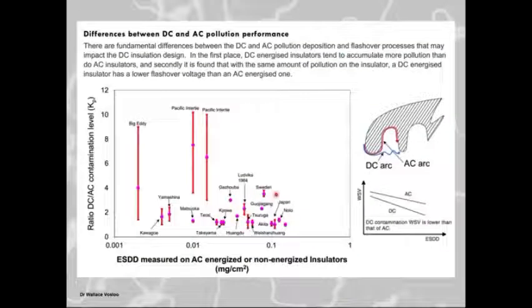Then when we take a look at the reason why, you find that when you look at the pollution accumulation of the ratio of DC to AC, you would see that there's far more pollution that accumulates on DC than AC, and it's got to do with your electrostatic forces drawing the actual pollution onto the DC insulator. Then further, also with the flashover phenomena, you find that with AC it tends to follow the surface, whilst DC it tends to jump across sheds, ignoring that creepage distance. So this definitely can give you an idea of the differences between AC and DC and the effect of the pollution catch on these differences.